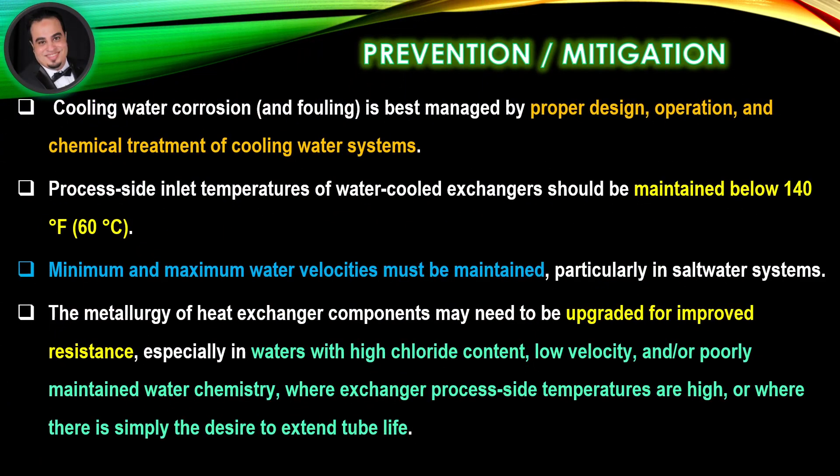Prevention and mitigation: Cooling water corrosion and fouling is best managed by proper design, operation, and chemical treatment of cooling water systems. Process side inlet temperatures of water-cooled exchangers should be maintained below 140 degrees Fahrenheit.